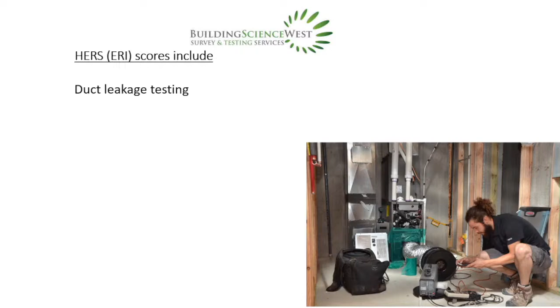We have a small computer slash pressure meter called a manometer, and that's all the brains behind it, telling you how much it's leaking. The formula for this, according to Utah code, is 6 CFM per 100 square feet of floor space that the system is servicing, and by code you have to meet this if 20% or more of the duct system is in unconditioned space.